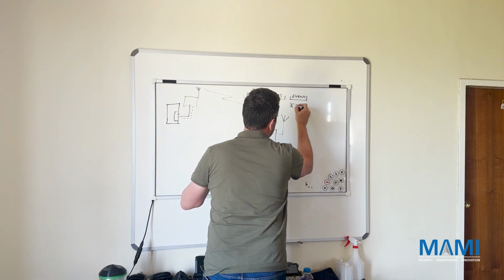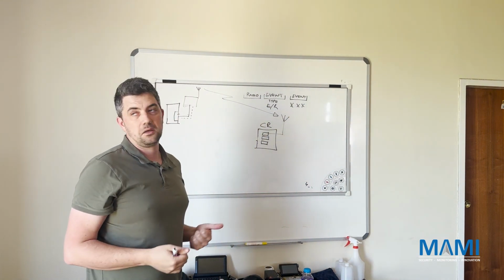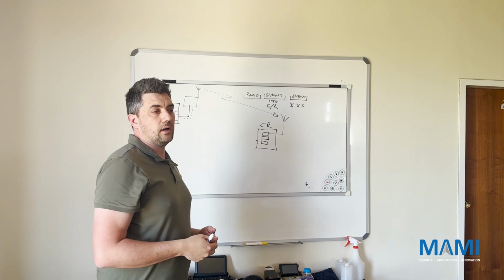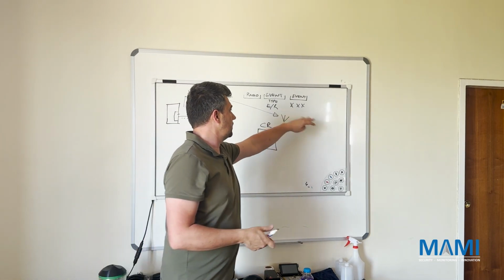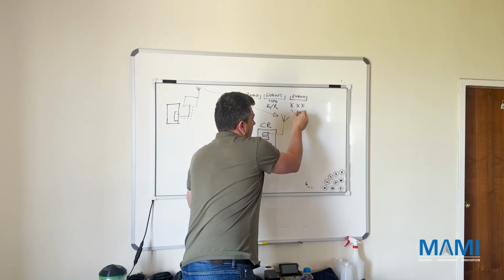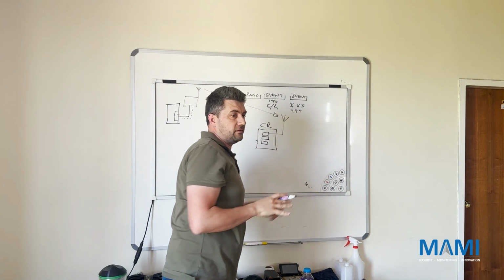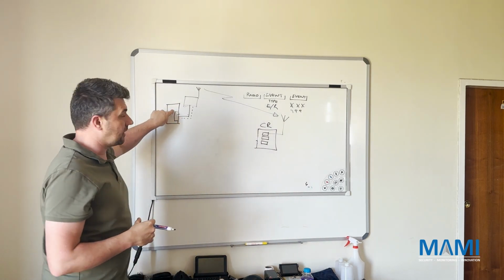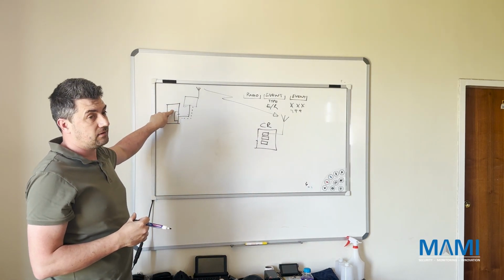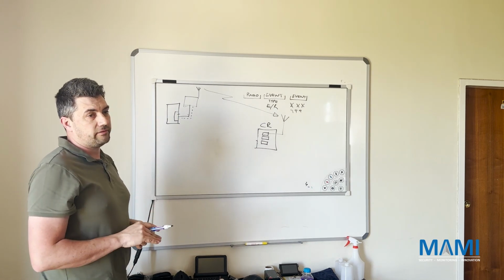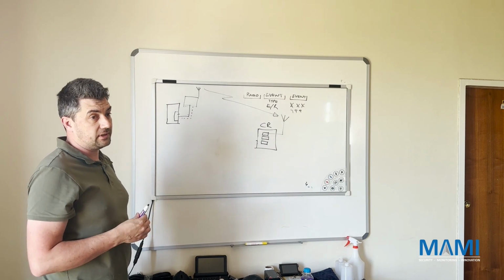And then here you've got 3 characters. I'll just put X, X, X, which identifies your type of alarm. So panic, medical, zone alarm, bypass. You know, so you've got a maximum of, say, 999 different types of events in ContactID. And in the same way, this doesn't actually mean an alarm panel. This could also be a fire panel. Anything that's dialing ContactID, it's sort of a universal format that everybody's adopted.